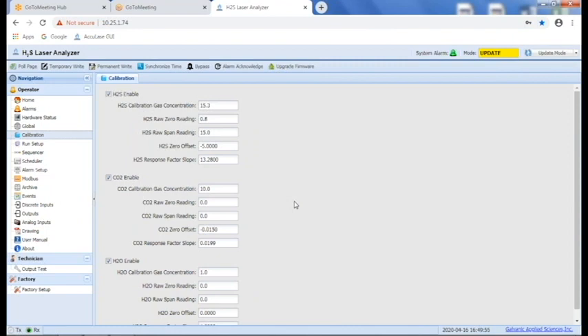The analyzer is offered with either one component or any combination of the three. So if you're only interested in H2S and H2O, for example, we would simply eliminate the CO2 and you would only measure those two components. So you can measure anywhere from 1 to 3.